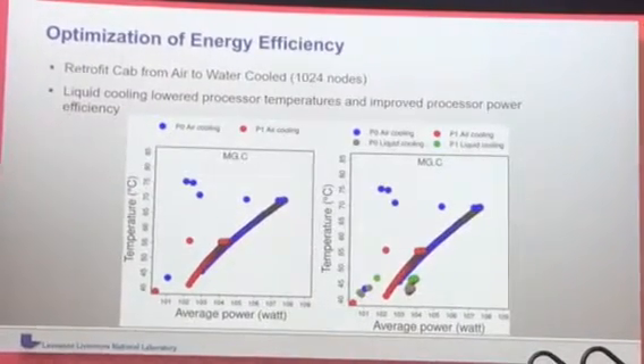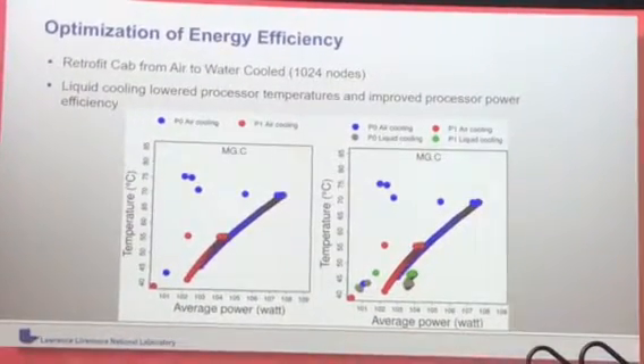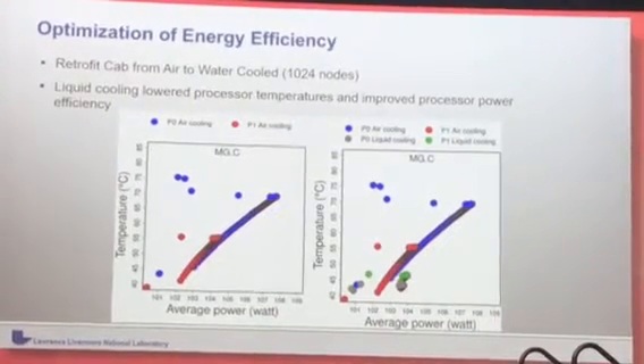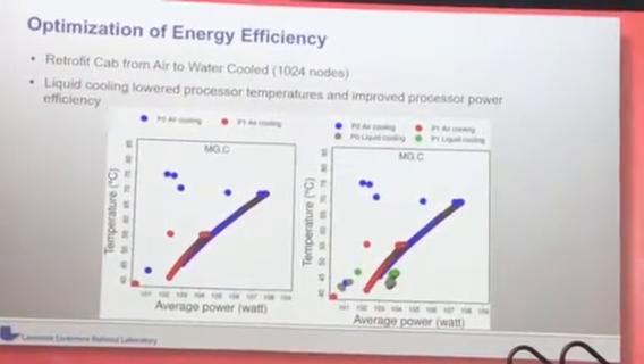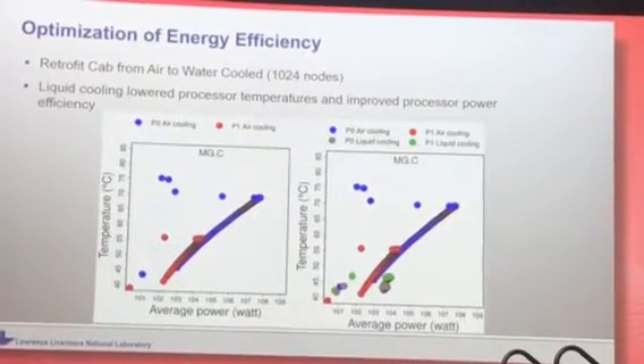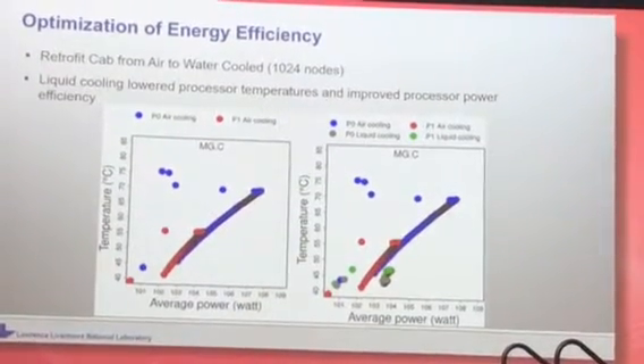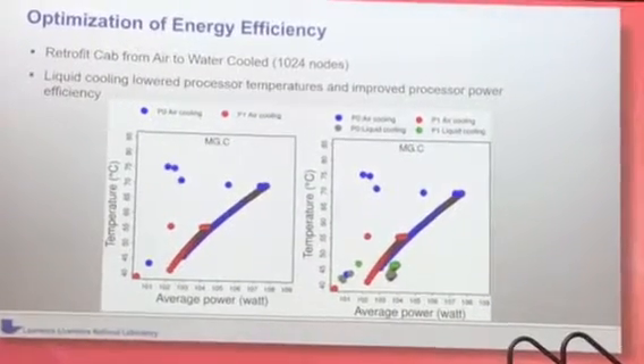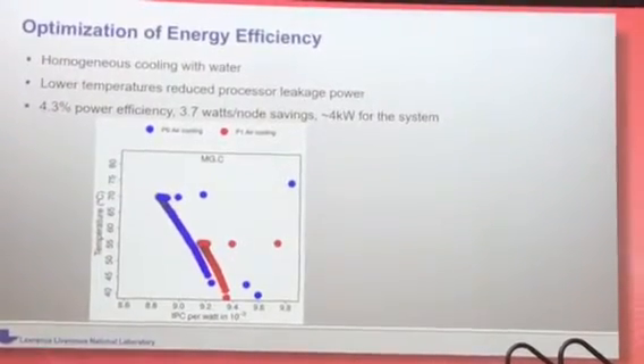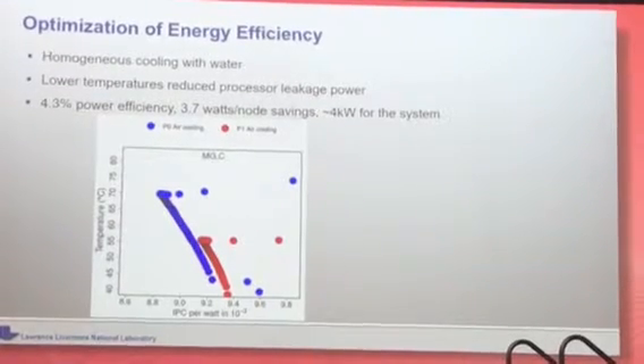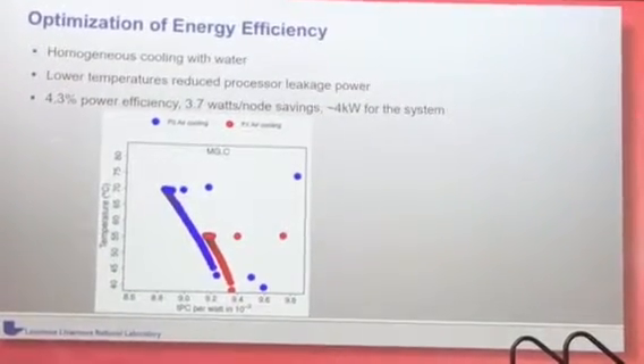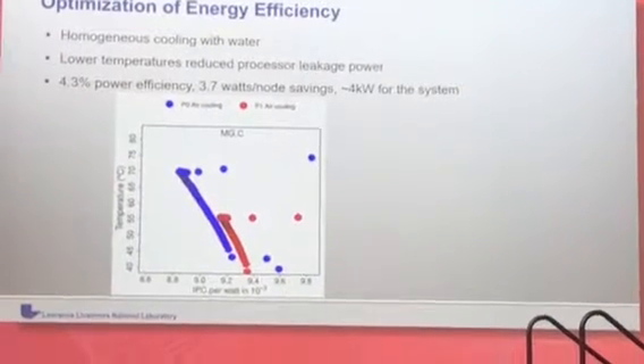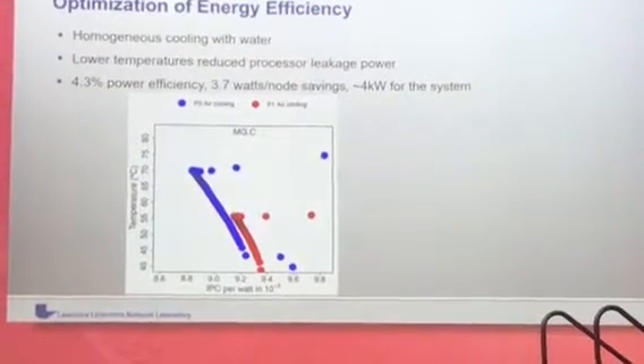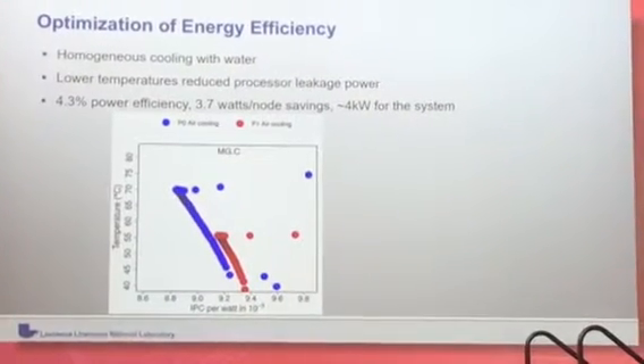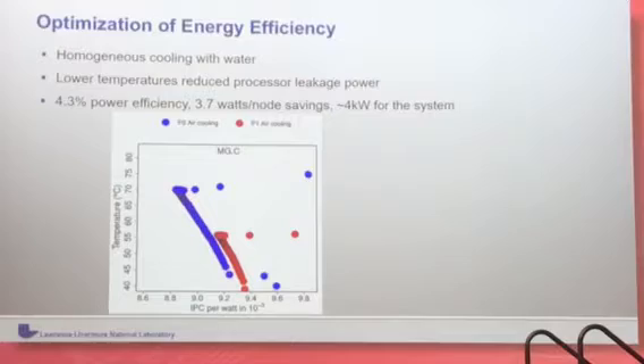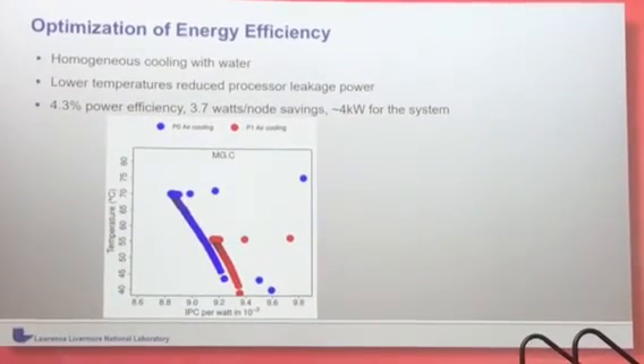But then once we made it water cooled, you can see in the green and the gray dots there that the temperatures are homogeneous. We're getting constant temperatures to each node, and all of the power usage is consistent. So it made it a lot more efficient. The lower temperatures reduced the leakage power and made the whole system more efficient. This is showing the efficiency of the computer. It's the instructions per cycle per watt.